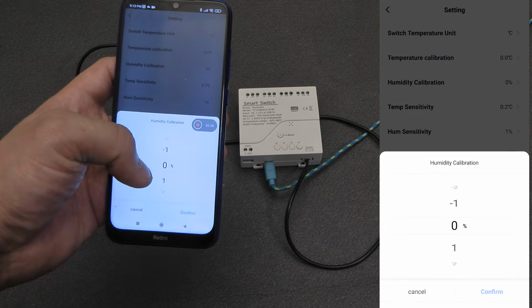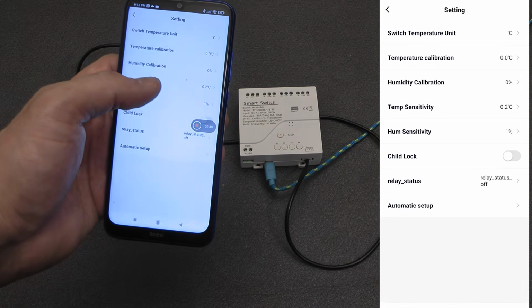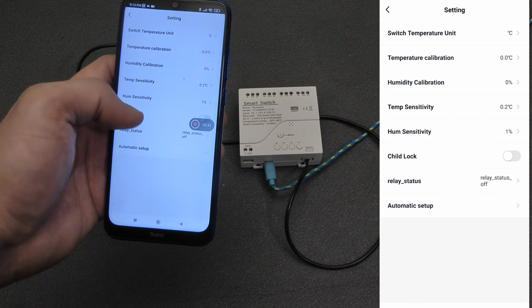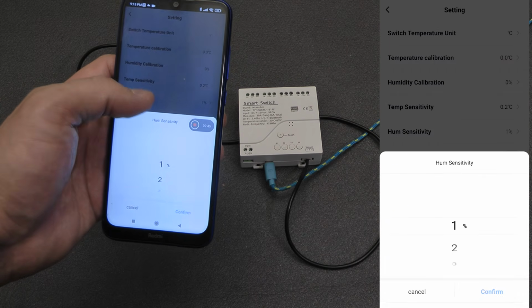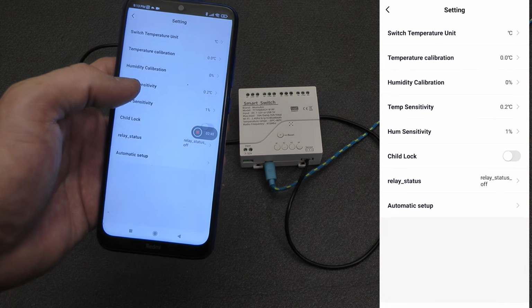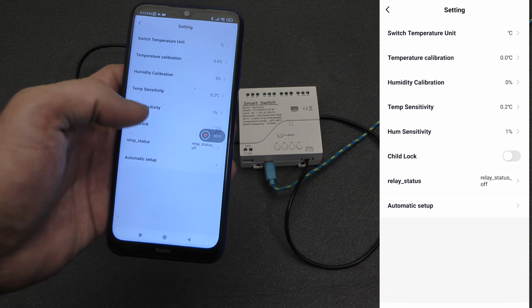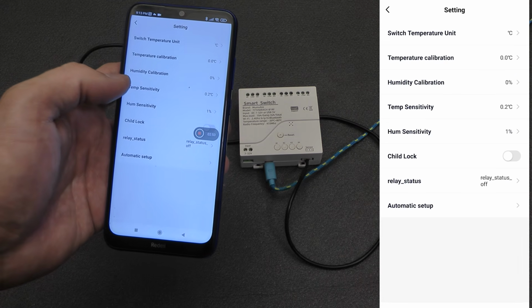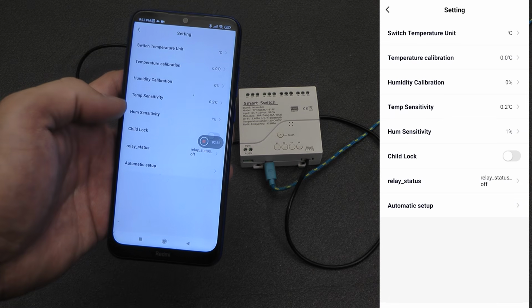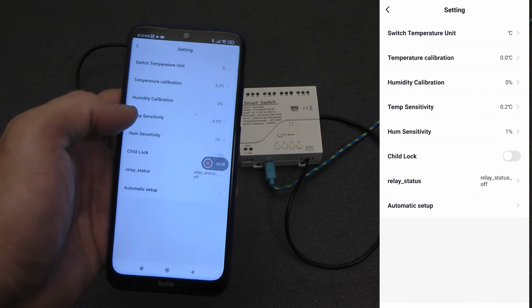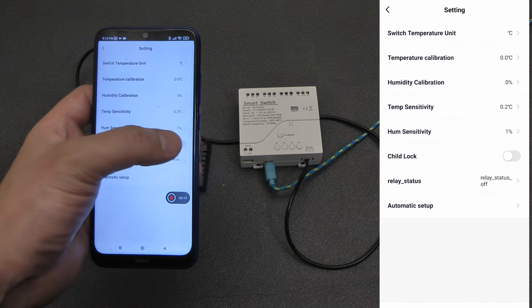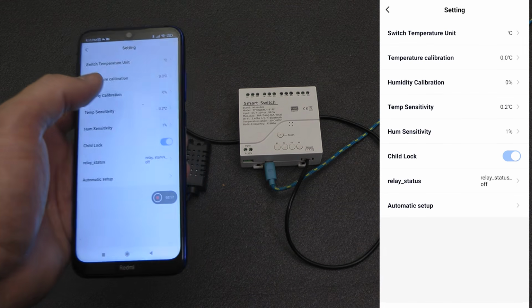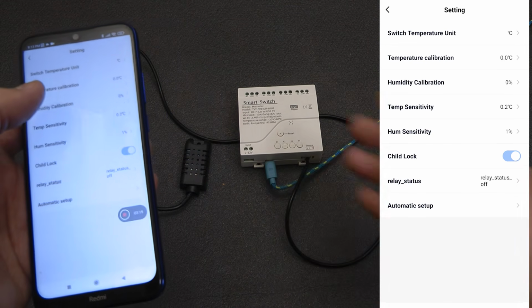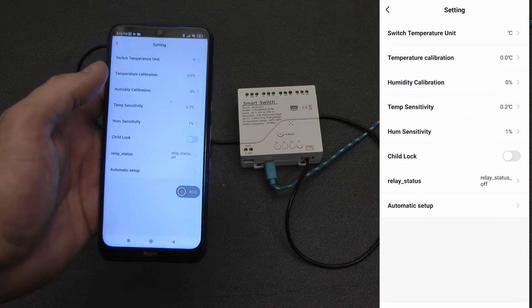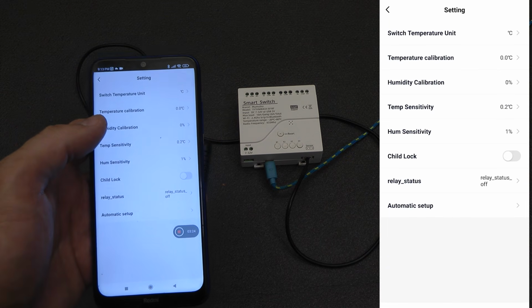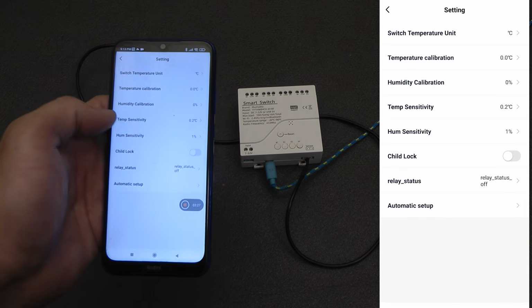Next are the temperature and humidity sensitivity settings. This is not calibration, but the minimum change in readings that the device will react to. For example, for temperature you can choose a sensitivity of 0.1, 0.2, 0.3 degrees and so on, and for humidity 1, 2, or 3%. The lower the value, the more often the device will react to small changes from the sensor. There is also a child lock function, which blocks accidental button presses on the body. This can be useful if the relay is installed in an accessible place and you do not want someone to accidentally turn a channel on or off manually.